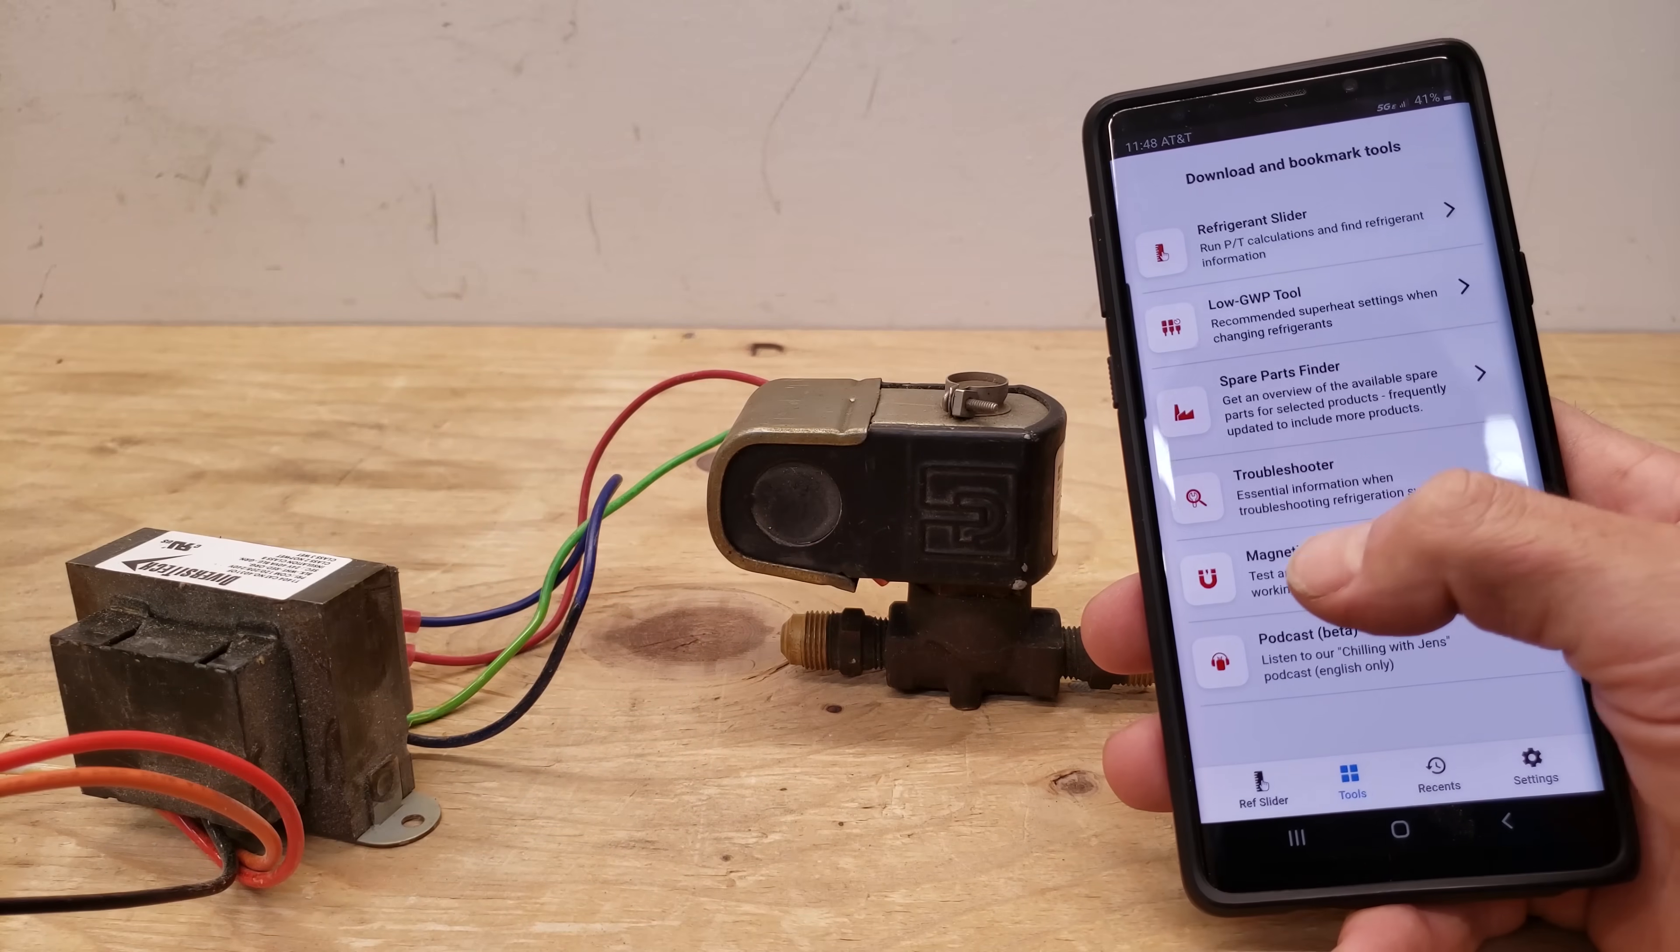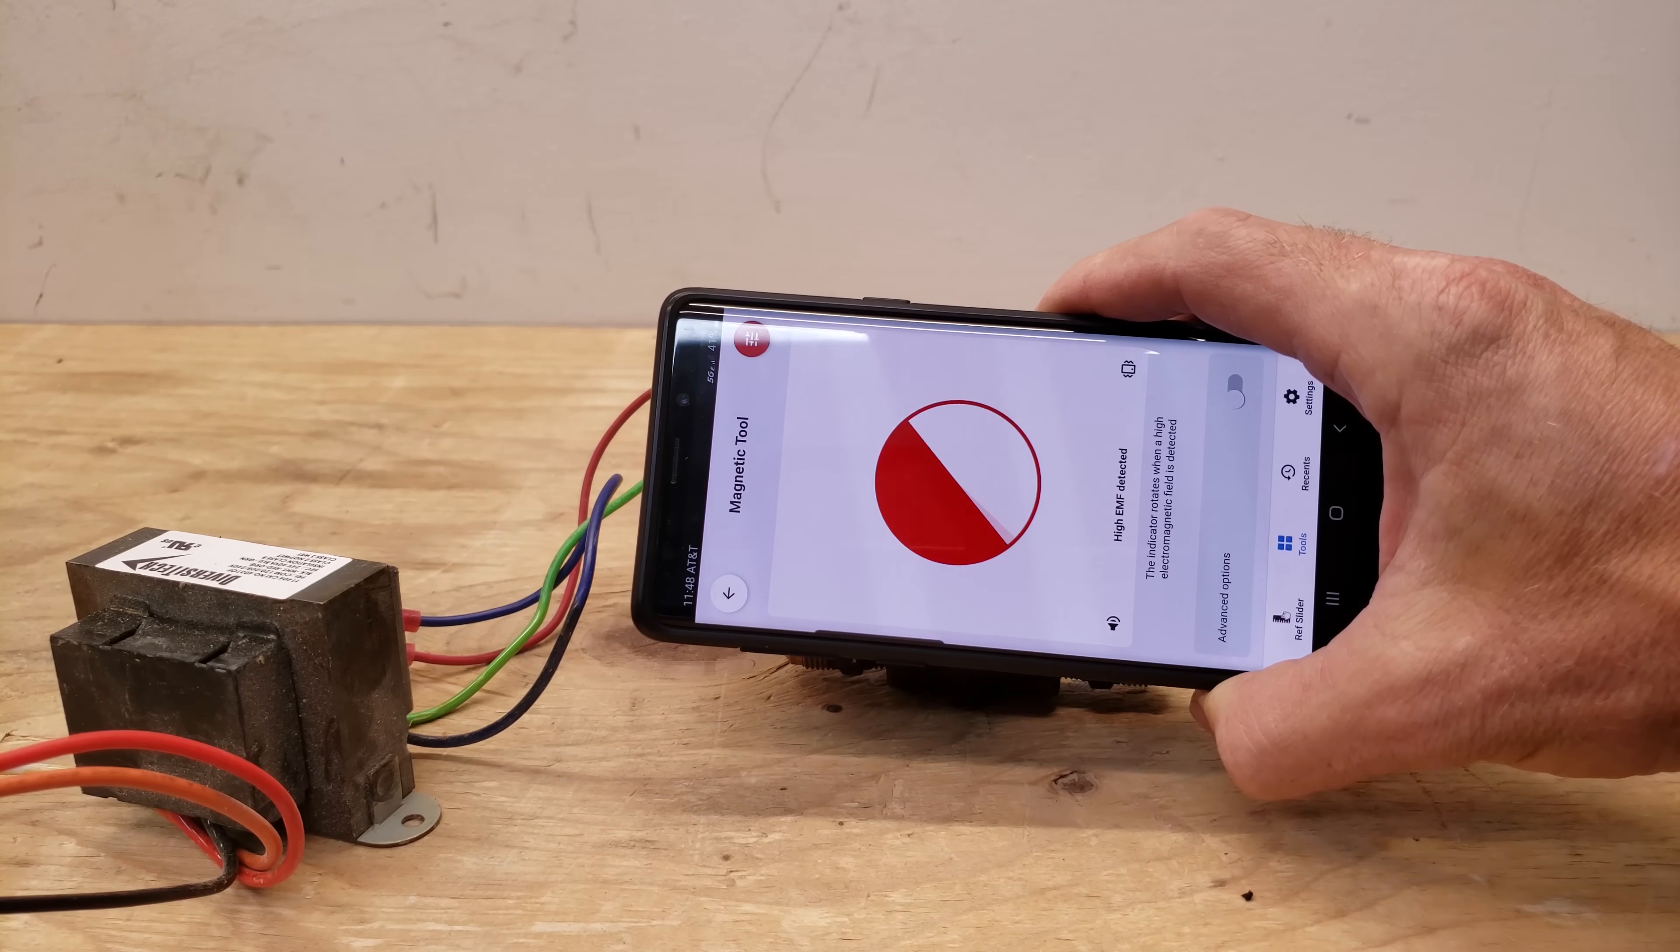Now let's look at the magnetic tool. You can use this tool for detecting EMF. If you put your phone or iPad right up near a solenoid, you can see if the solenoid has power to it or if it doesn't. You'll see this rotate when the solenoid has power and then you'll see it stop rotating when it doesn't have power. You can use this for any type of coil whatsoever. You can also use it on something like a circulator pump and you can see the actual direction of the rotation. You'll know whether the circulator pump is on and you'll see the rotation of that.